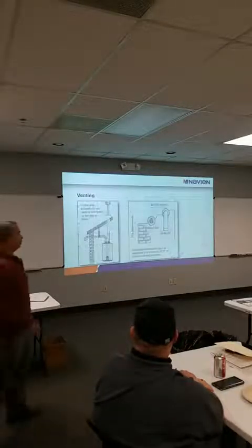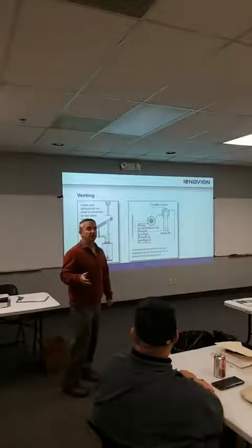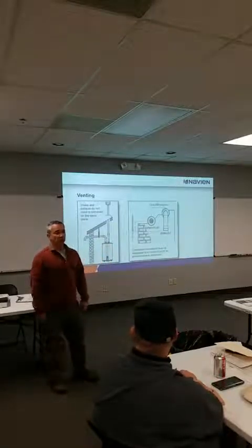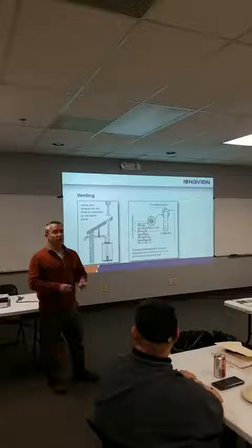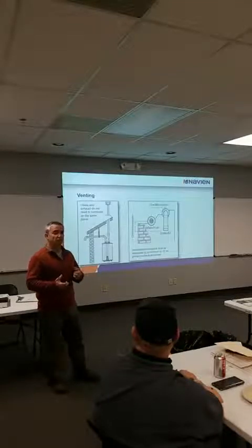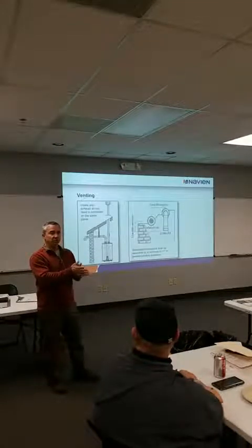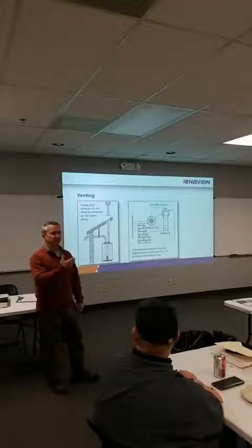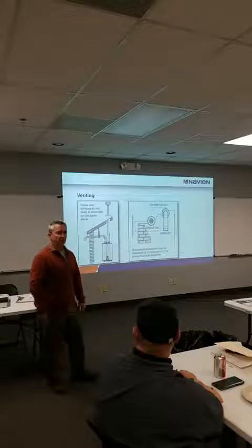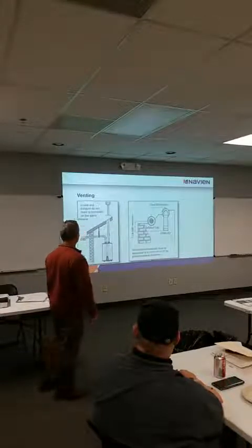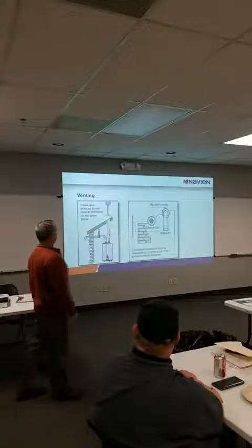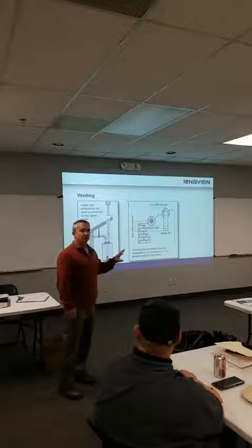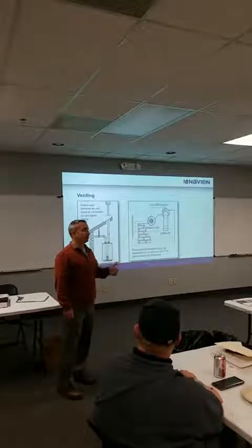So to be clear, you don't need equal distance, and they don't need to be on the same side of the building? Nope, we don't care. Windage doesn't matter. You can use concentrics, horizontal or vertical, and you can use those flat plate concentrics, every one but the bay vent. We don't like the bay vent, it freezes up, and I don't know if it's just our problem or our engineers just don't like it. All the dimensions are in the book, but we're pretty liberal when it comes to venting.